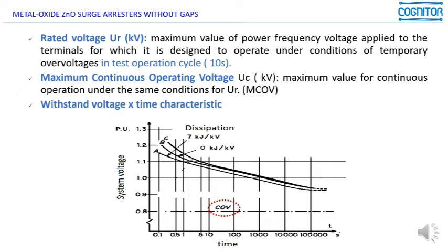138 kV phase to phase is something like 145 kilovolts. Then even for these very high values that can occur in one substation during certain parts of the day, of course the surge arrestor should not discharge, should not permit the passage of the current. It should work as one infinite resistor in this condition.